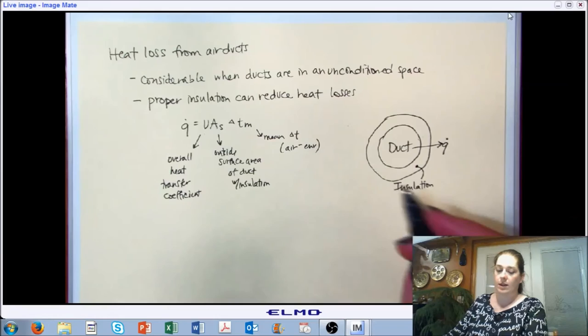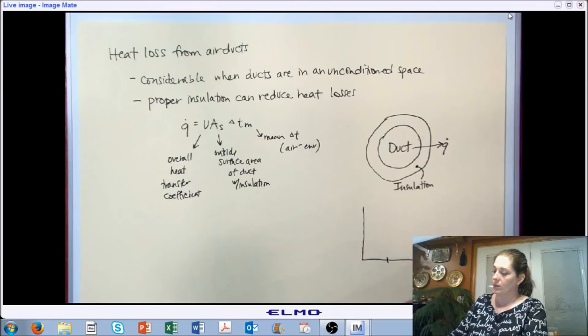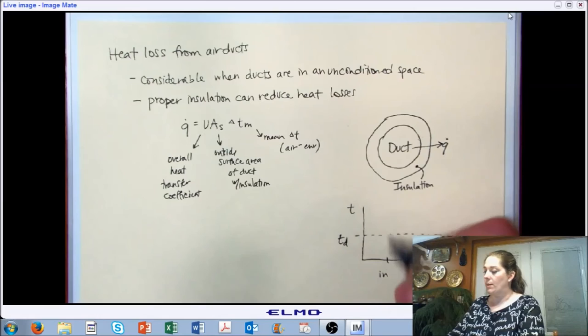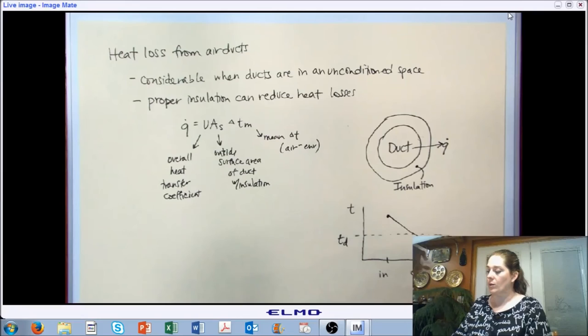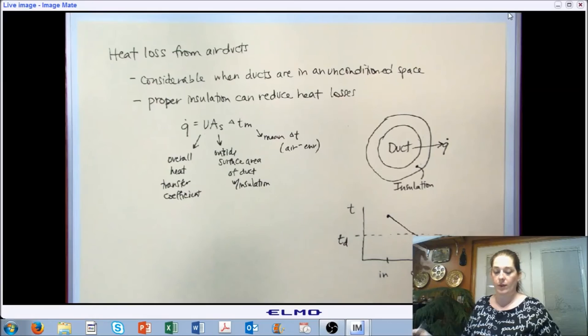You also want to be careful to avoid condensation inside your insulation. Monitor the dew point temperature: if the dew point occurs within the wall of your duct, you're likely to get condensation inside the insulation. Make sure the dew point temperature does not occur within the duct wall — keep indoor and outdoor temperature profiles in mind when evaluating this.